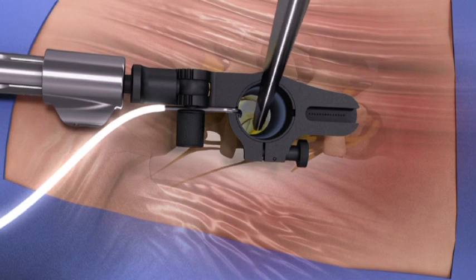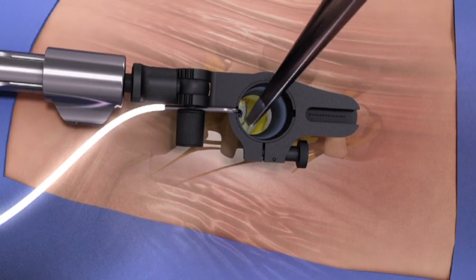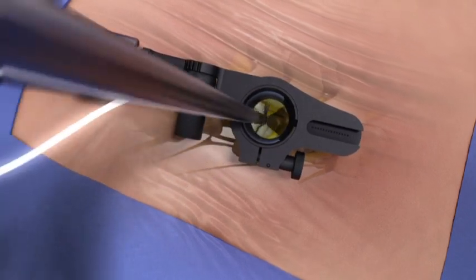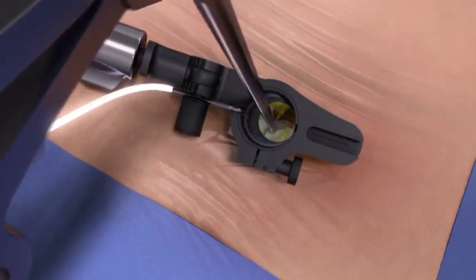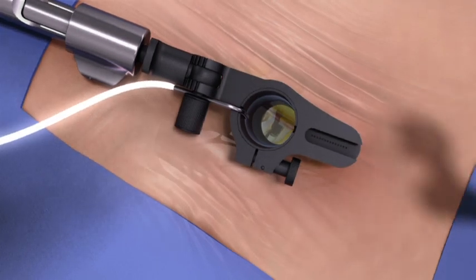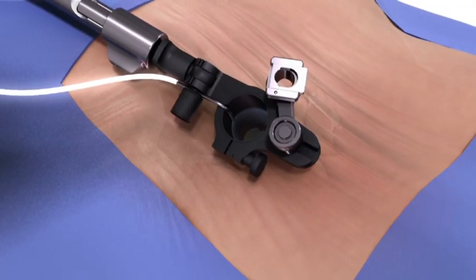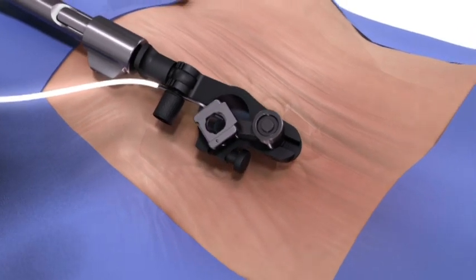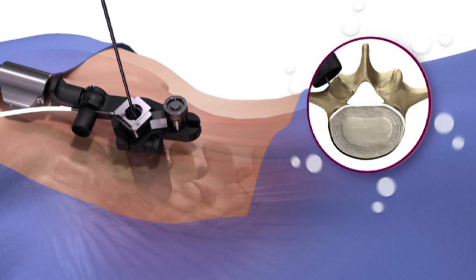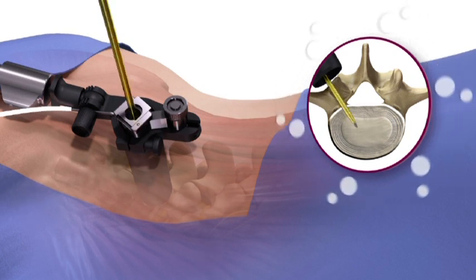Bony exposure, decompression, and discectomy can be performed using a combination of conventional surgical instruments or with the Spineology OnePass system. To use the OnePass system, connect the I-beam to the track in the top of the retractor. Introduce the guide pin through the I-beam and into the disk space, followed by the dilators and access portal.